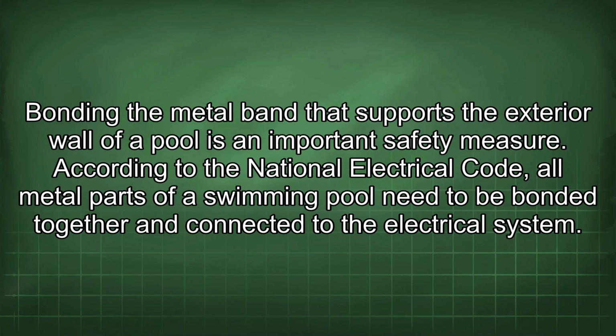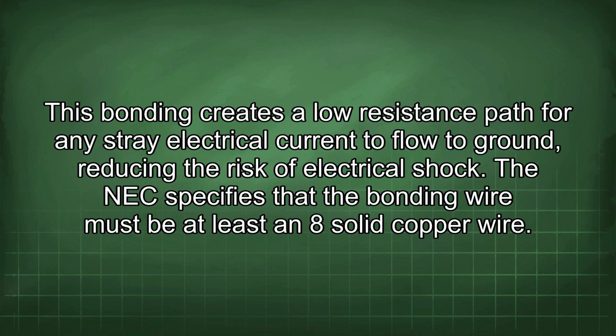Bonding the metal band that supports the exterior wall of a pool is an important safety measure. According to the National Electrical Code, all metal parts of a swimming pool need to be bonded together and connected to the electrical system. This bonding creates a low resistance path for any stray electrical current to flow to ground, reducing the risk of electrical shock.